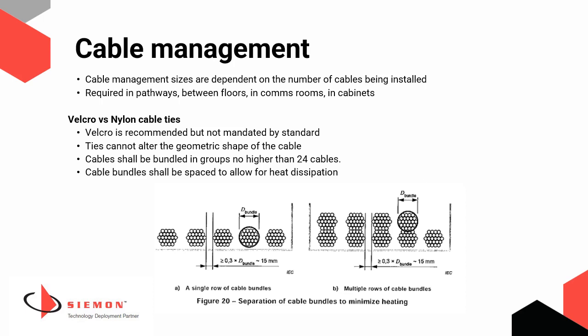In this graphic, we show the recommended number of cables in a bundle and how they should be installed. Bundles to a maximum of 24 cables should be spaced in the tray in order to provide airflow through the tray. These bundles should be tied every 3 meters using Velcro. Nylon ties are allowed as long as they are not cinched too tight where they alter the geometric shape of the cable. Please note that in a lot of specifications, the use of nylon cable ties is not allowed, so please be aware and please refer to the specification.